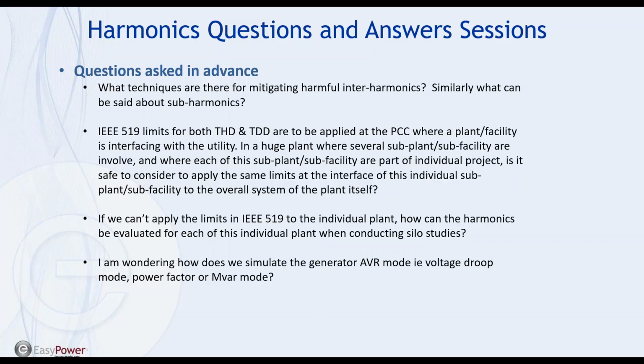And then again, looking to achieve 5% voltage distortion throughout the entire facility would be another design objective. Okay, next question. If we can't apply the limits in IEEE 519 to the individual plants, how can the harmonics be evaluated for each of these individual plants when conducting silo studies? So I think you can apply 519 distortion limits. It's not going to be a requirement by your local utility, but again, it's just a good design practice to do so.